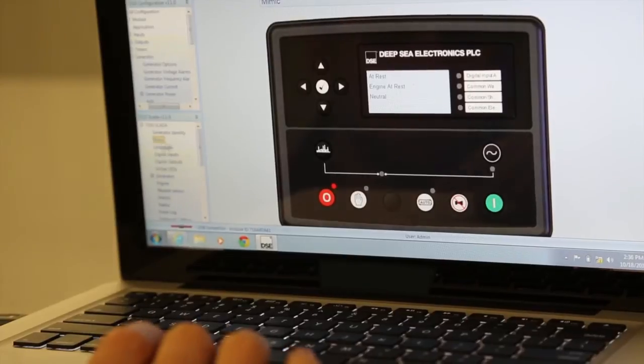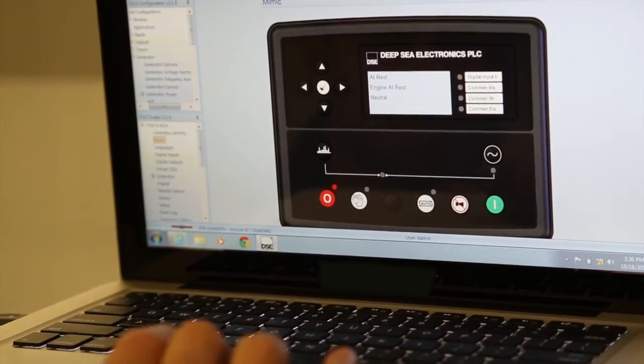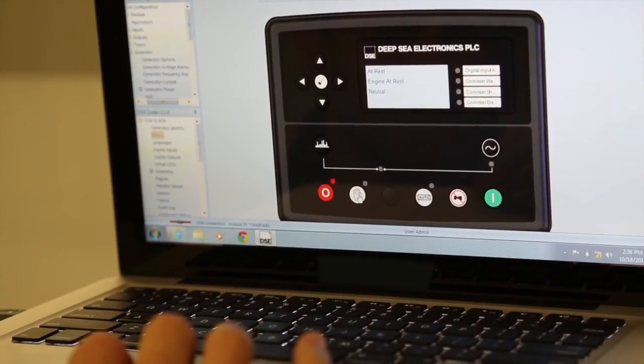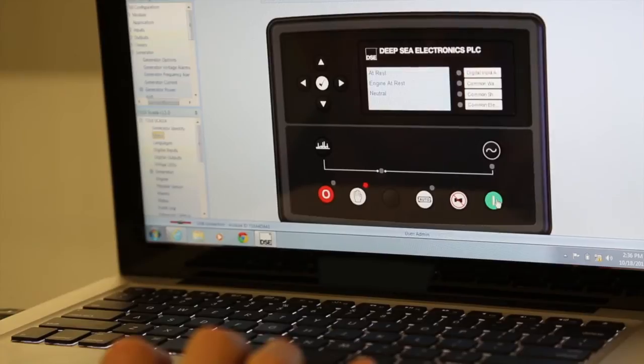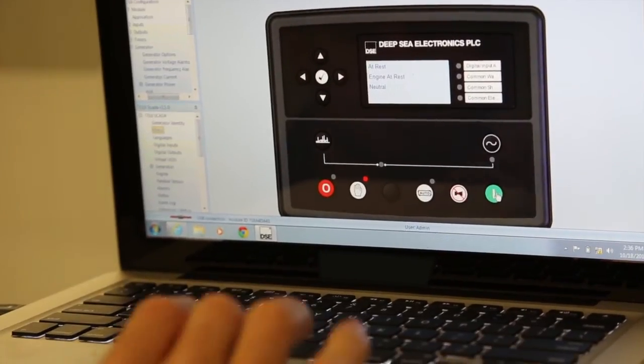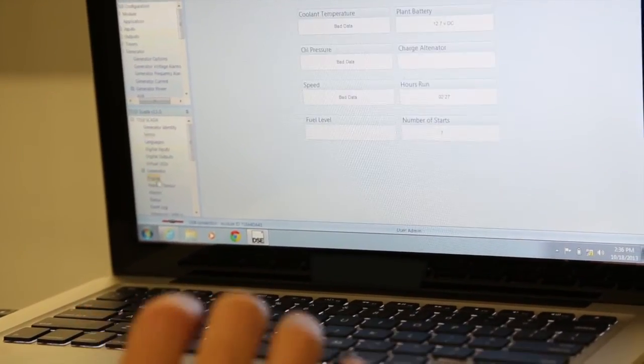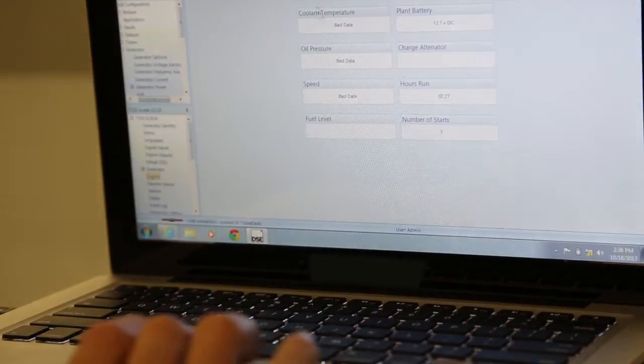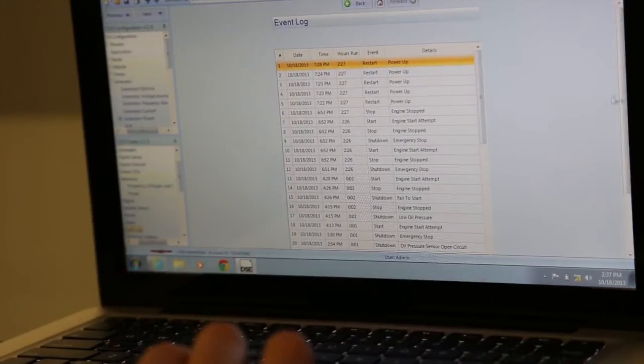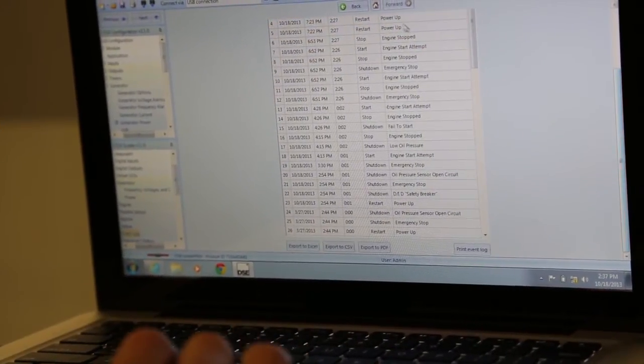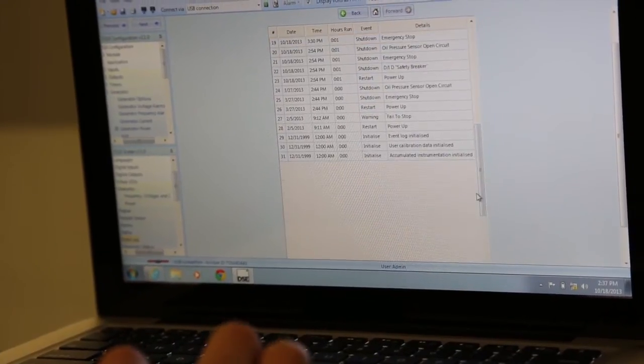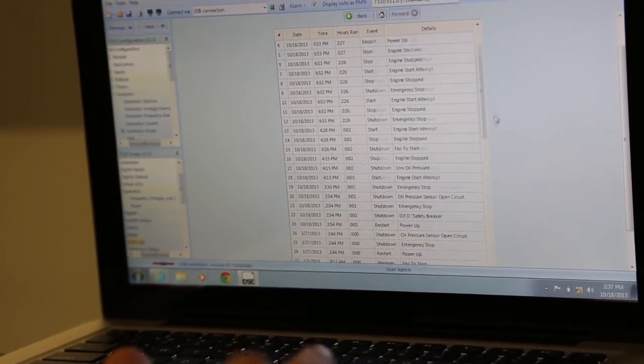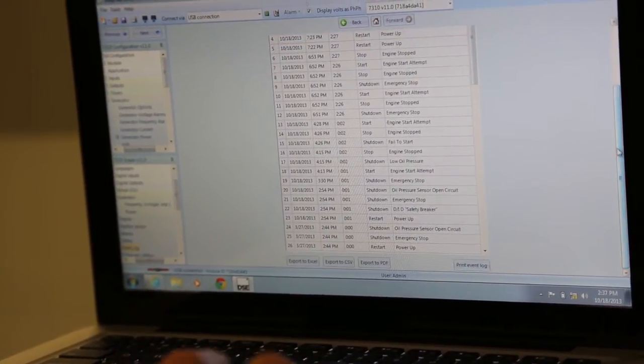As mentioned earlier in the video, the mimic screen option gives you the ability to start and stop the machine, to view various data, to see multiple parameters on one single screen, to view any alarms, and to download the event log. Once you have access to the event log in the status menu, it will bring up all the events stored in the event log up to 250.